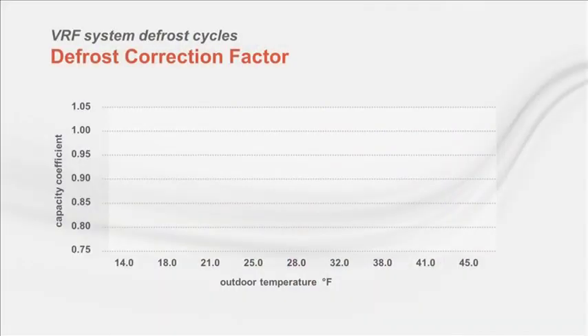This slide shows one manufacturer's capacity correction because of the defrost cycle. Defrost affects energy use also. At best, it provides no useful heating, but still runs the compressors to thaw the outdoor coil. There's little that can be done to reduce the defrost energy. With some engineering judgment, a chart similar to this could be helpful when implementing the defrost portion of energy modeling.